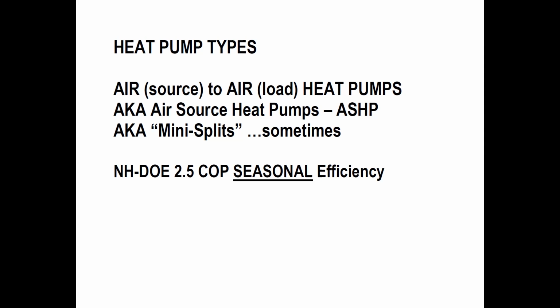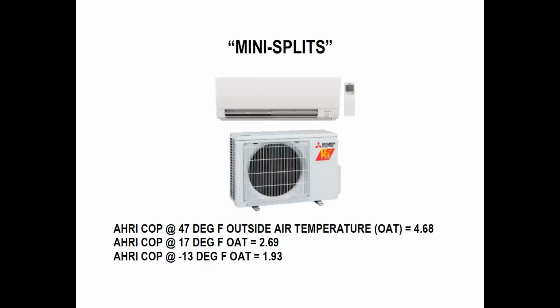Seasonal efficiency is based upon where you live. In New Hampshire, the New Hampshire Department of Energy says that over the period of our heating season, the average efficiency is going to be 2.5. And that's because it's a variable amount of temperature outside every day. Let's go to, I think the next one is just a picture. So this is a picture of your standard heat pump. I don't get any kickbacks from Mitsubishi, but this is a Mitsubishi. There are lots and lots of brands.